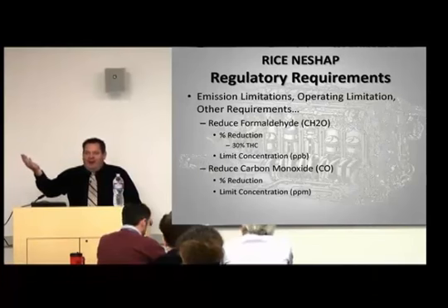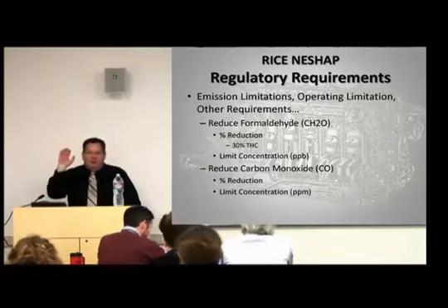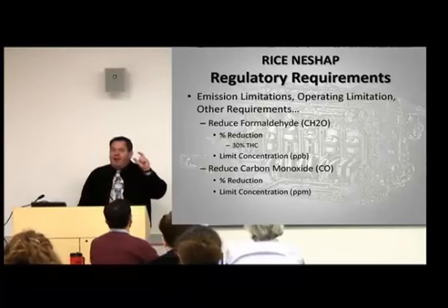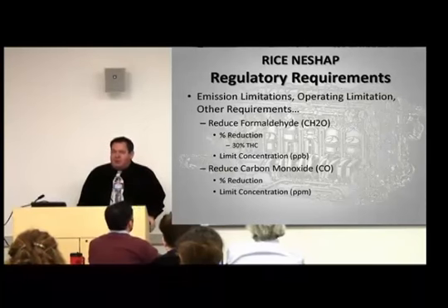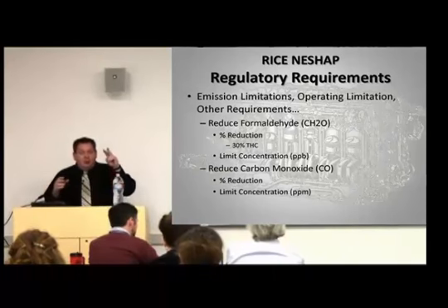Nobody thinks of formaldehyde. So the industry came back and says, oh, come on, this is very burdensome to us. You got to change this. So with these recent updates on the 14th or 15th of this month, whatever the case may be, you're allowed to have a 30% hydrocarbon reduction for engines that used to require 76% formaldehyde reduction, and there's also a CO option for those engines. So in terms of carbon monoxide, there's two options.